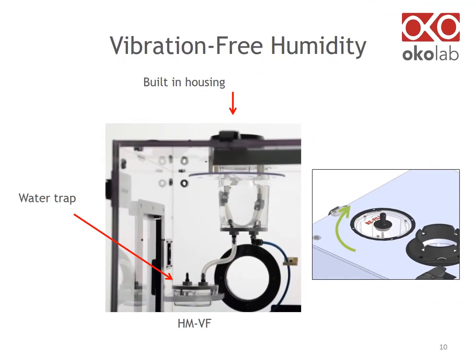A vibration-free humidity module has a built-in housing in the enclosure. The water container can be refilled from the outside without opening the enclosure, avoiding temperature perturbations. This is optimal for most applications, but if you're imaging an open dish — meaning without a lid — you must use an active humidity system.